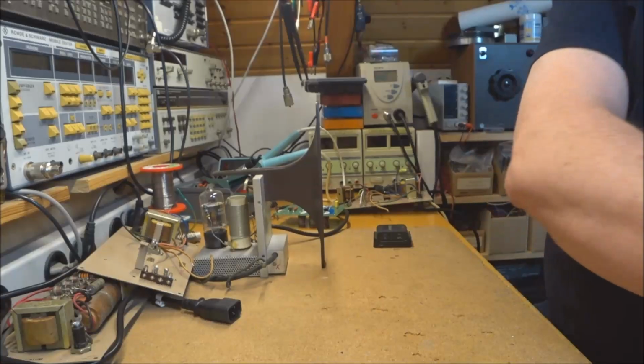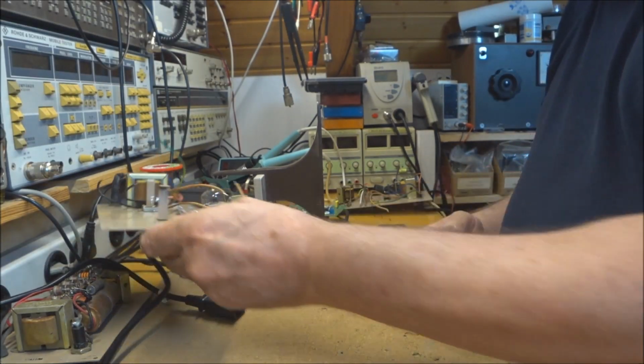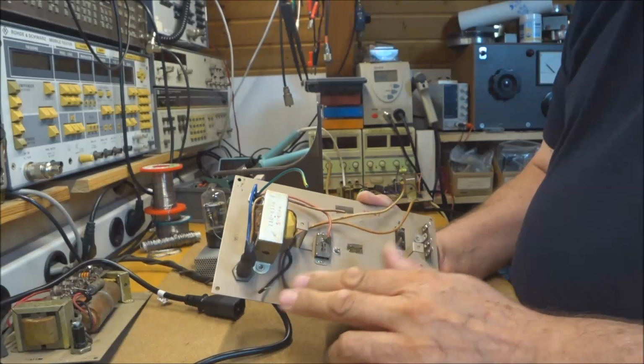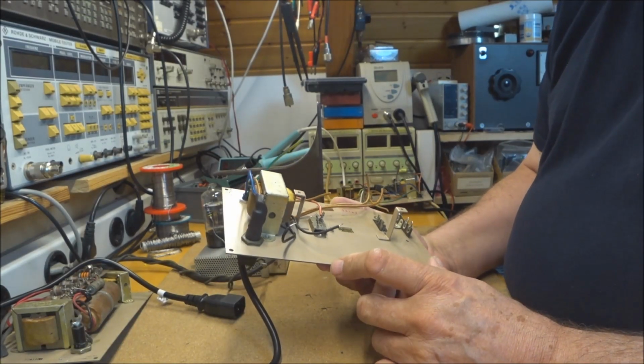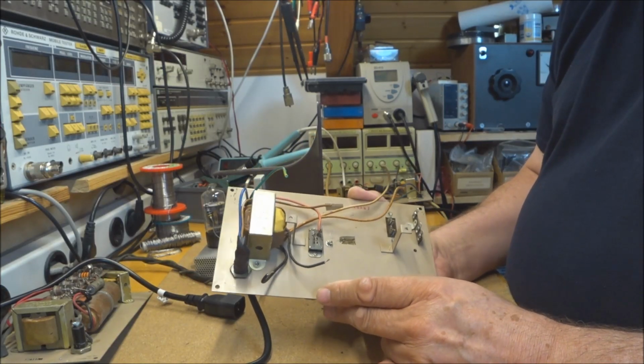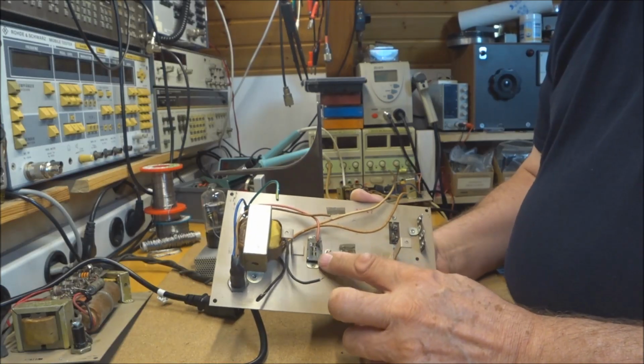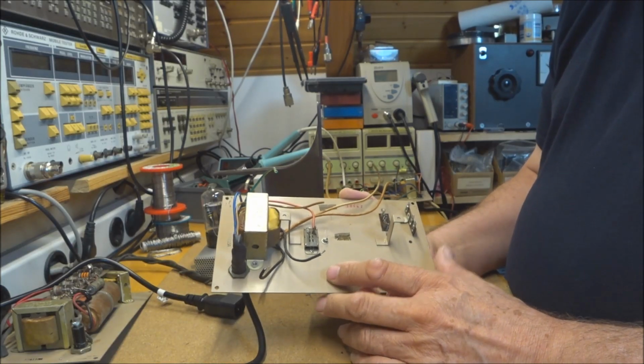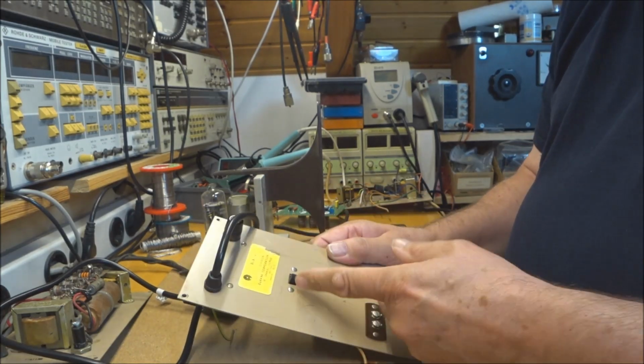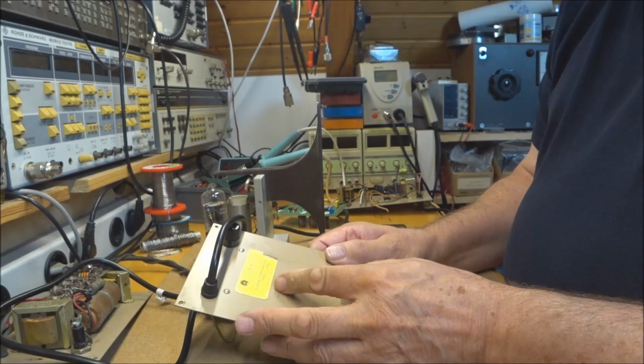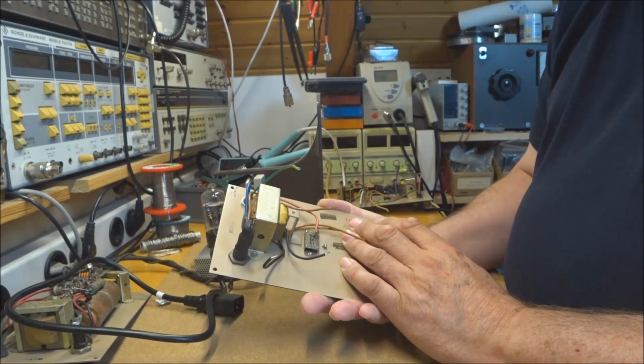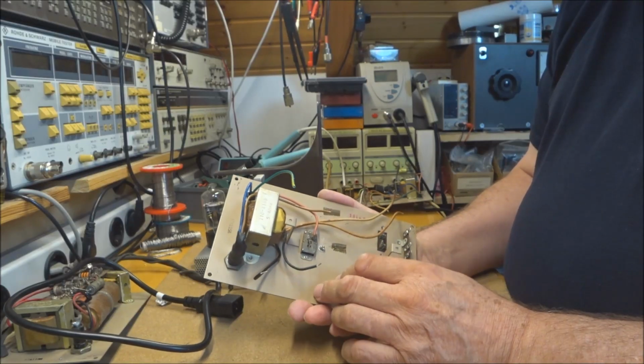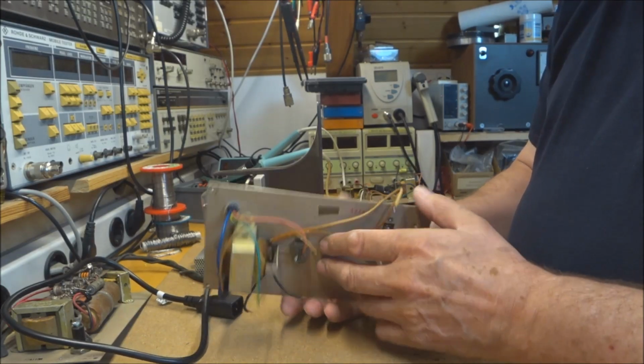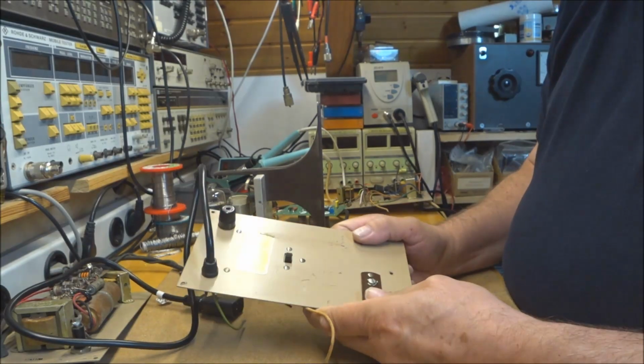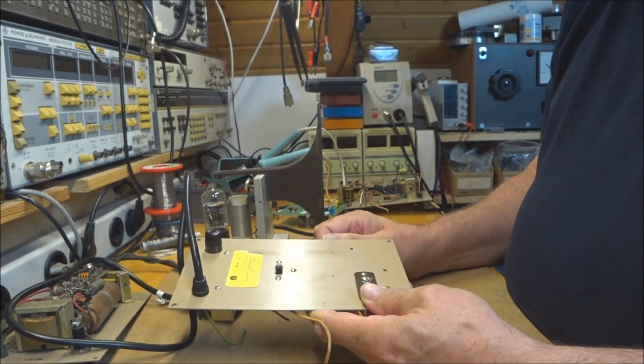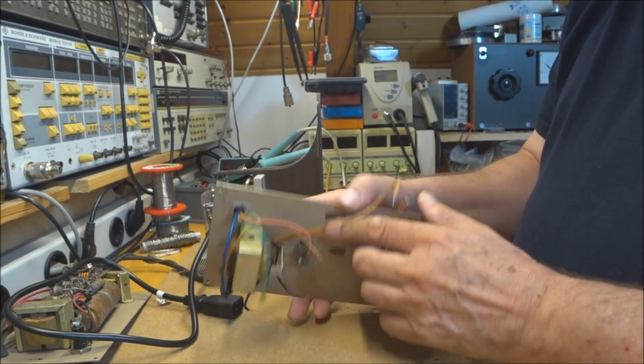By the way, one word about these old main power switches: in 80% of cases, these main power switches are defective because they don't give contact. They are dirty inside, and you have to open them and clean them, and in 80% of cases they are not making contact anymore. So this is something you have to look out for.